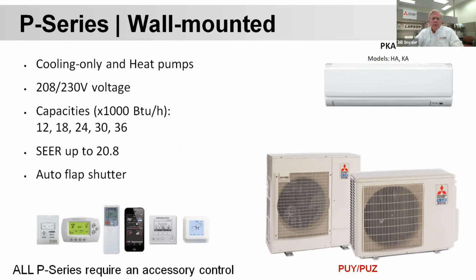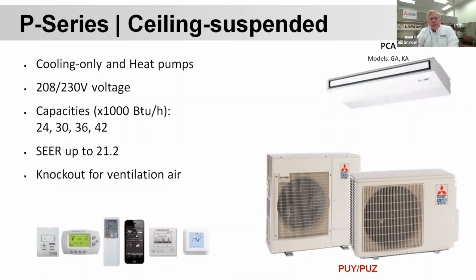-40. So on that model number nomenclature that we talked about, if it ends in a -7, it's capable of going down to -40. So this is what you would use in like a server room, elevator equipment room, that sort of thing, where you need cooling even in the very, very low ambient conditions. Okay, the P series, same thing. Ceiling suspended unit is the same thing. That's capable of, if it's a cooling only, doing low ambient cooling down to -40.